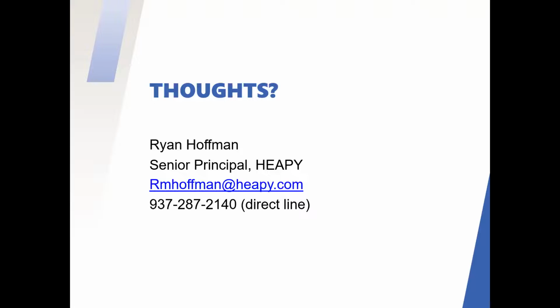We usually frame it in terms of percent of total utility cost or consumption. I wouldn't say we go into every building thinking 15% is achievable, that's what was mentioned from Energy Star, and I do think it's achievable in some buildings. But the first step is a conversation with the building owner to understand how they're operating the building today. Basic questions like: is the building scheduled? Is it taking advantage of resets? Do you have an ongoing maintenance program or service agreement around the building control system? And understanding the customer's willingness to make changes to how the building operates today. All of that together usually points us to a rule of thumb percentage that's more customized or specific for that individual project.